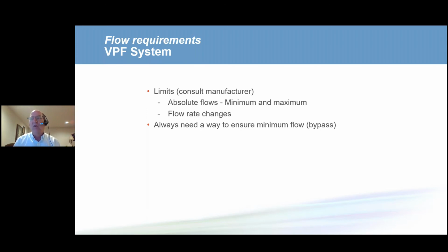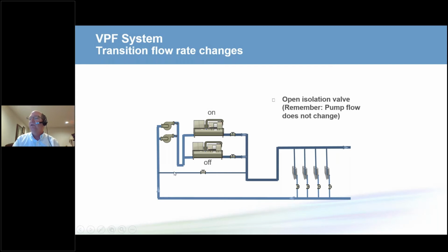So those two are very important from the product standpoint. Then you always have to have a way to ensure the minimum flow rate. Most of the time that minimum flow rate is done using a separate bypass line and valve. On small jobs, it could be 3-way valves in the system to maintain the flow rate. But those aren't the hardest parts about a variable primary flow system. Here is the more complex part. Again, system controls take care of this, but we have to consider it. In this system, when we turn an additional chiller on because the cooling load has gone up, nothing changes from the pumping standpoint, because the pumps are still responding to the flow rate that the system and the coils need. So the only thing that happens to turn that second chiller on is we open the isolation valve on that second chiller, it proves flow, and that chiller can now turn on.